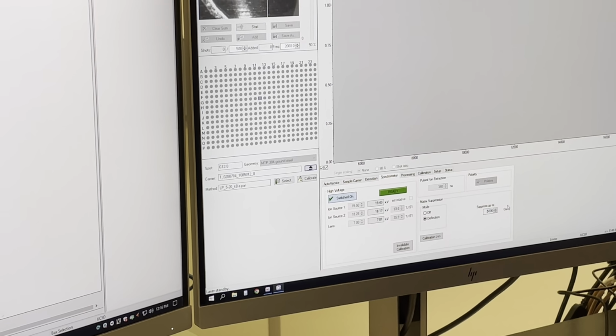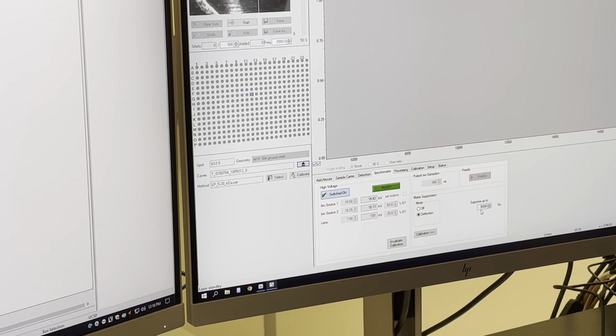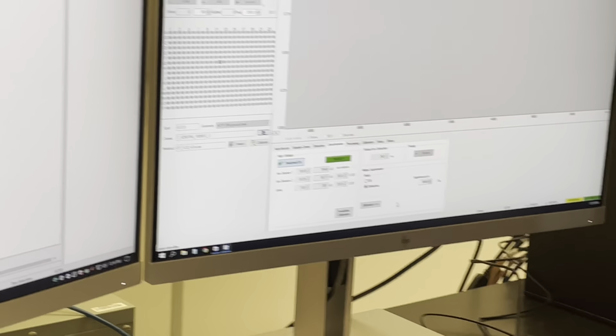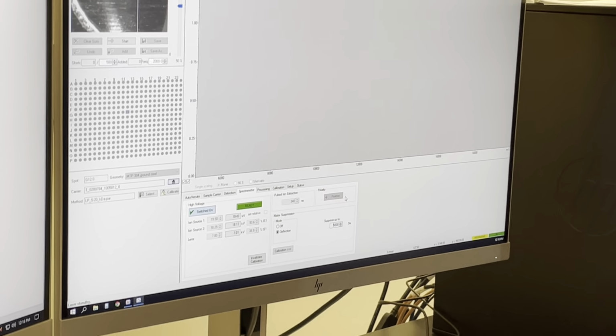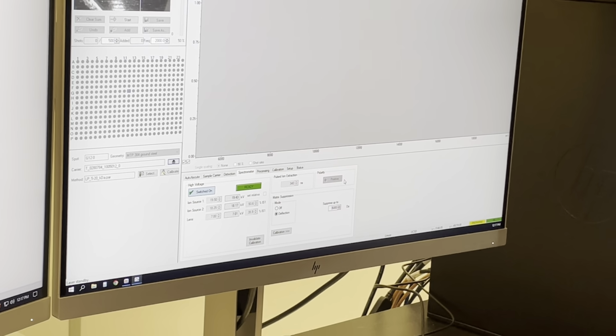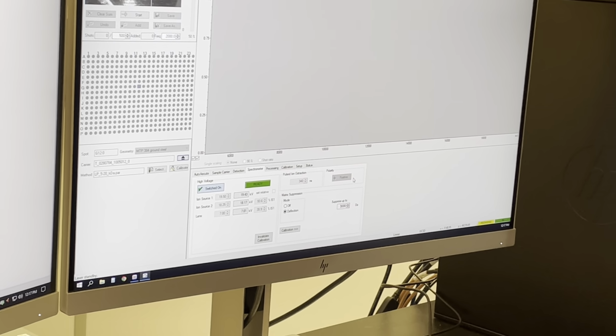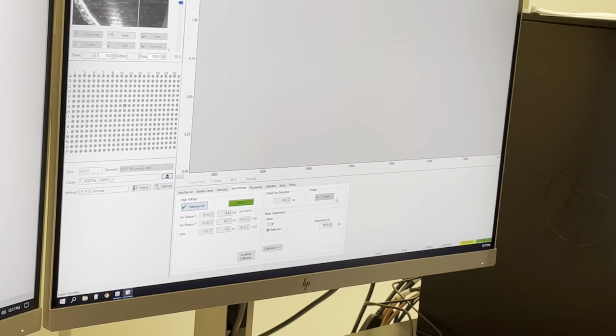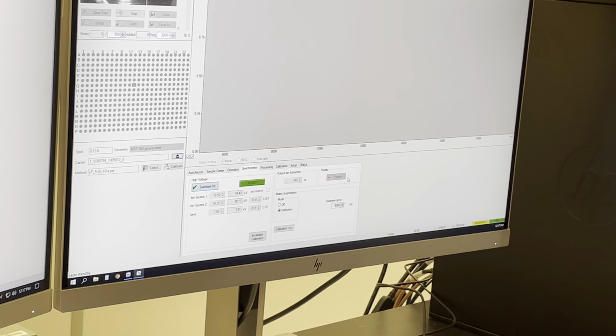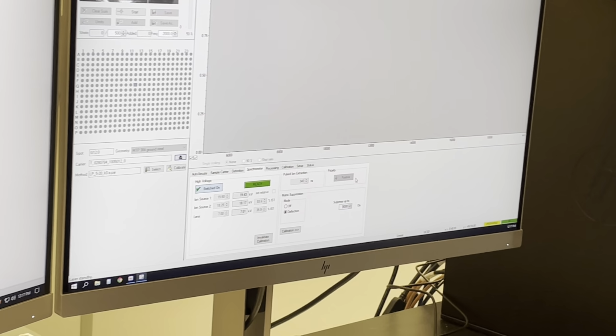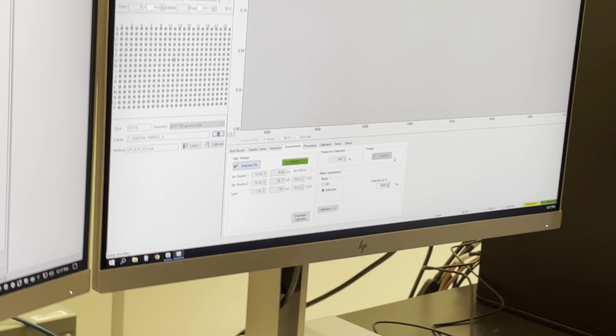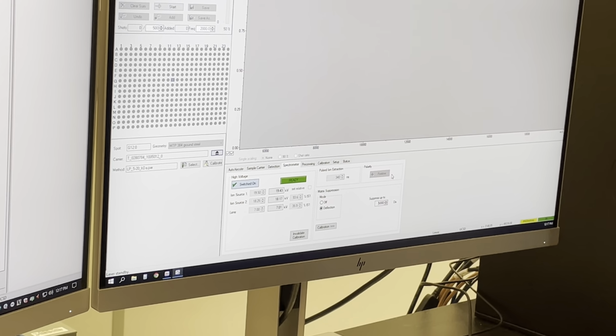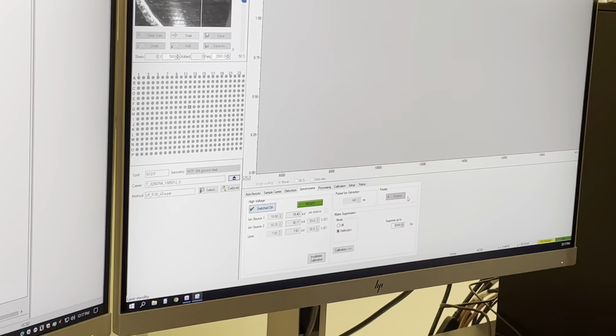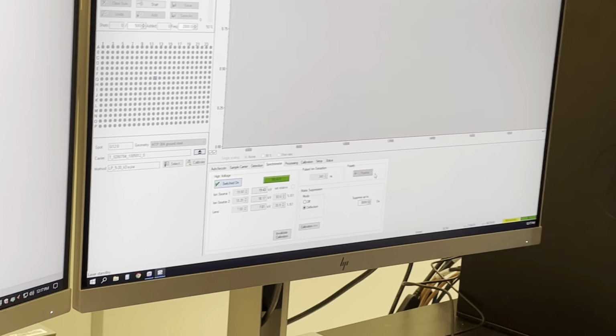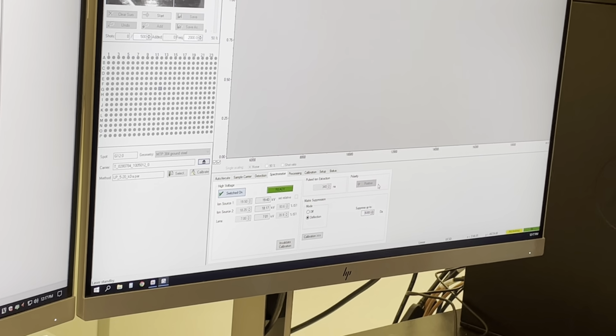What you need to do is double check this value. The default is 4,000. But if you are interested in something, for example, between 10,000 and 20,000, you can set it to 8,000. The reason to have this is that if you have something below 8,000, the peak may be very intense, and it's going to suppress the ionization, or the peak of your protein of interest may not be very obvious. Also, the main peak is very intense.